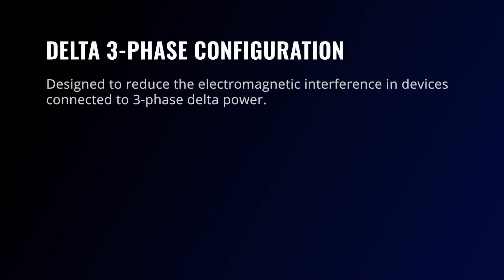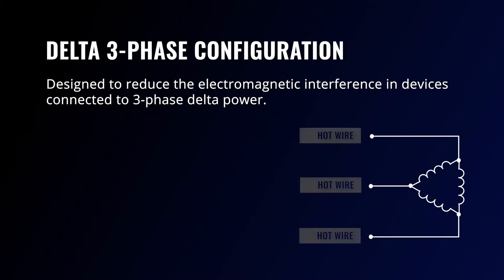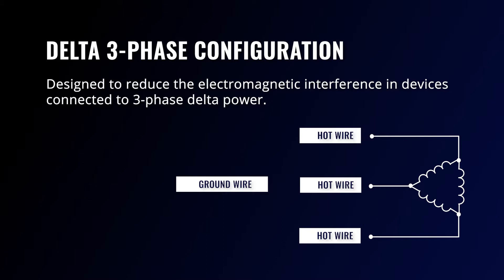Delta three-phase EMI filters are designed to reduce electromagnetic interference in devices connected to three-phase delta power. The delta configuration contains four wires: three hot conductors and one ground conductor. The phase loads are connected to each other in the shape of a triangle, where the connection is made from one end of winding to the starting end of the other, forming a closed circuit. This configuration does not have a neutral wire, but it can be fed by three-phase Y power if the neutral line is grounded. The delta system can be used for power transmission, and the absence of a neutral cable can also help reduce cost.